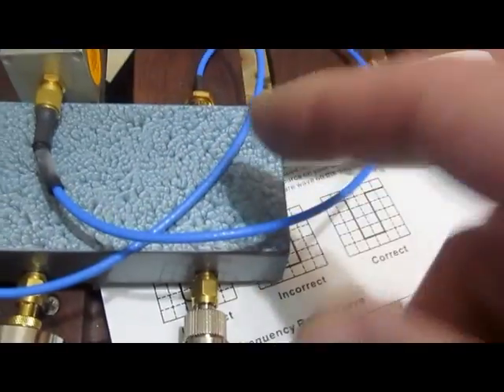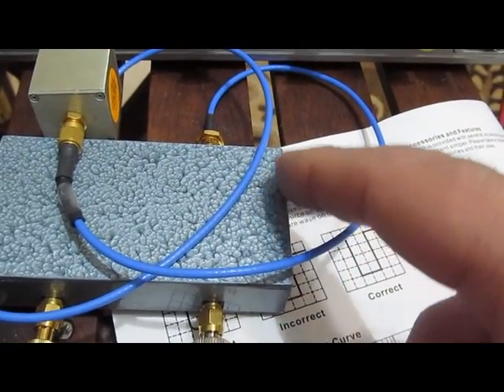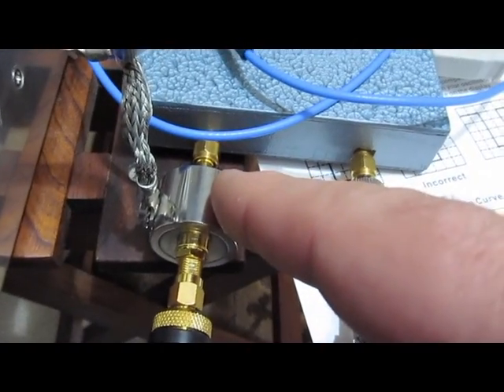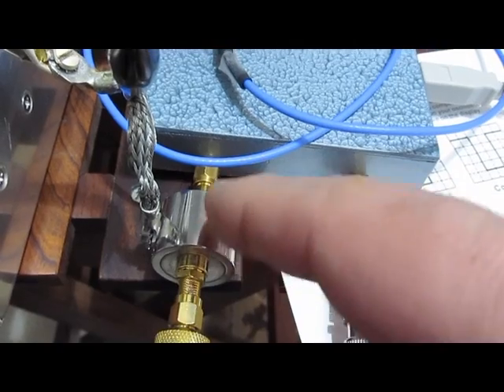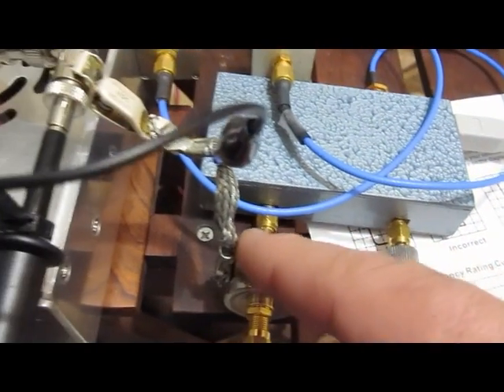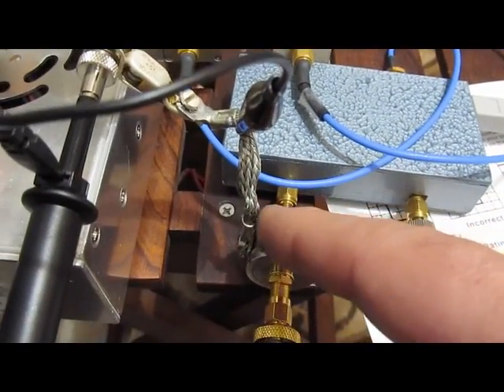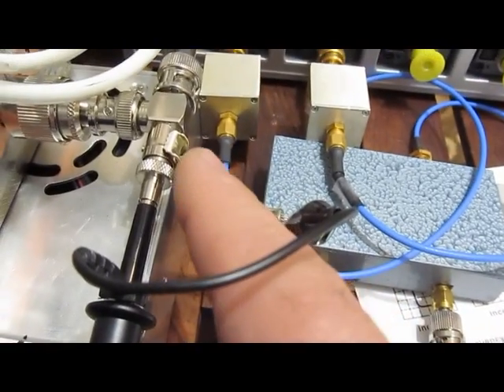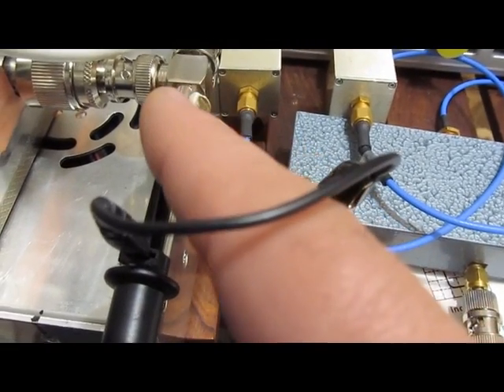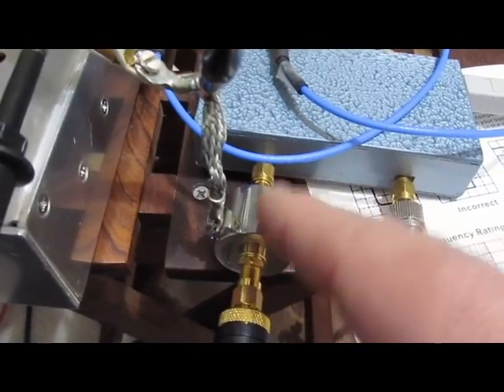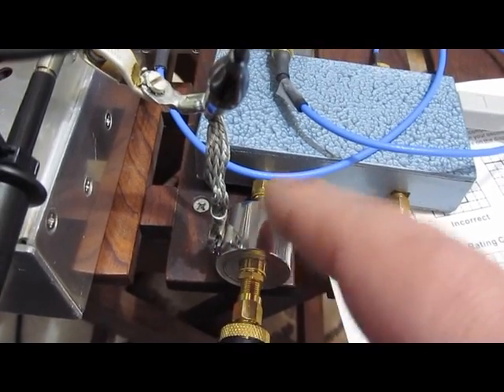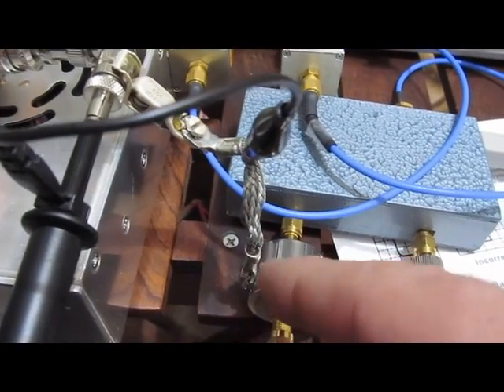Coming off the dummy load, we have another sense point. It's going through a fairly good attenuator and I use that as a monitor. In this case, the monitor signal goes through a 50 ohm pad, then into a buffer amplifier. So the probe goes through this Citel clamp. This is a gas discharge tube, fairly low voltage. And you can see our strap. This runs back up to the BNC. So if this probe is to arc, when this tube breaks down, this is going to close the loop.